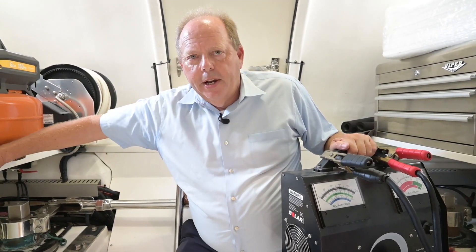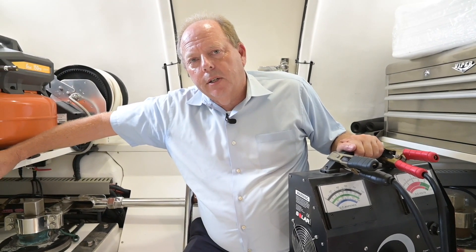Now we're going to go upstairs, turn off the charging circuits. Step one in this exercise is to physically look at the batteries. Step two is to take away charging capability and see what the resting voltage is. If a battery is in really bad shape, when you take away the charger and leave it for a while, it'll go way below its normal voltage. That still doesn't tell you if it's in great shape, but it tells you it's not totally dead.